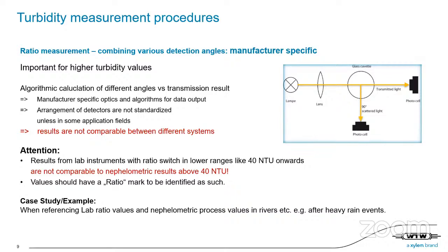So for every other value, it is a ratio measurement. And therefore, you must be aware that they are not comparable. Values are not comparable between a nephelometric measurement with 90° above 40 NTU with those, or above any limitation at that point. And all values should have a mark of ratio, because this means other than nephelometric measurement for drinking water with defined regulations and optics, this is a manufacturer-specific arrangement and detection. So these results are never comparable between different systems.